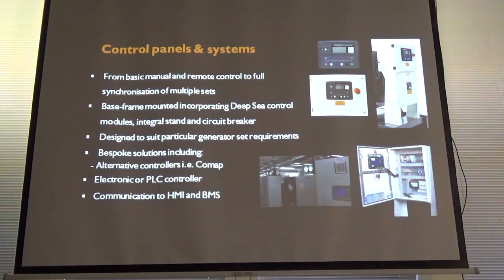COMAP, PLC controllers. We've just secured an order last year, just under 6 million. That's five 2.5 MVA emissionised units, three in one plant room, two in another. Attenuation level 52 dBA at one metre. The implication of that, as I mentioned, with the attenuation, is the inlet attenuator bank is 7 metres long alone. 7 metres. And it's offset, so you've got the primary stage up to about here, then an air gap, and the actual splitters are offset. So if you look through, you can't see, because they're staggering the air paths again as well. But 7 metres, again, that's the key thing.